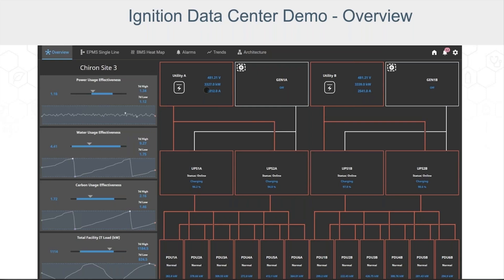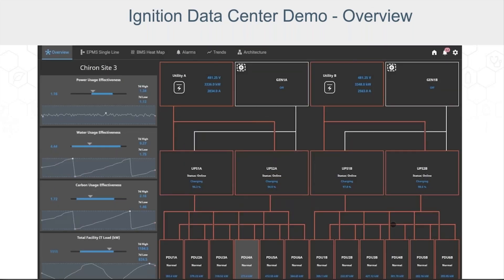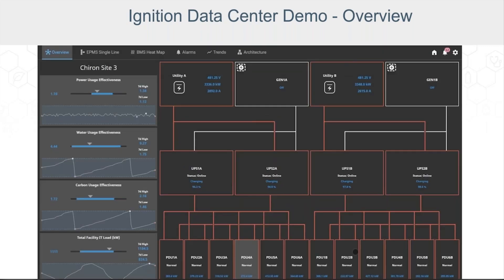This specific view focuses on electrical infrastructure and includes power quality meters, generators, UPSs, and PDUs. The red colored lines designate the power is on, or hot, and that the equipment is energized. Each piece of equipment is also clickable, which brings up a pop-up to show more detail and metrics for that specific item, including any active alarms. In future releases, we expect to scale out the application — this overview will likely depict multiple sections within a data hall, or even multiple data halls as you might find in a hyperscale facility. The design concept is to show key metrics and status at a glance, without the extra complexity of a single-line diagram or engineering schematic.